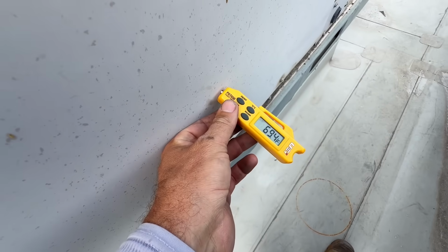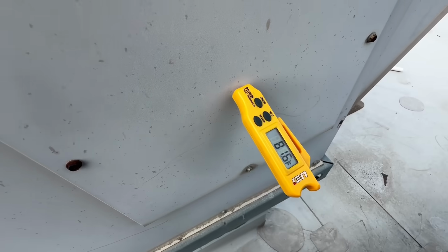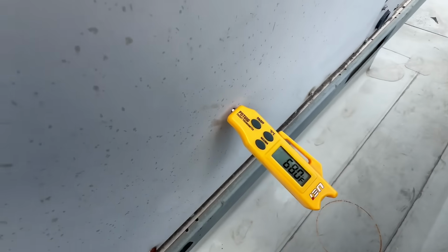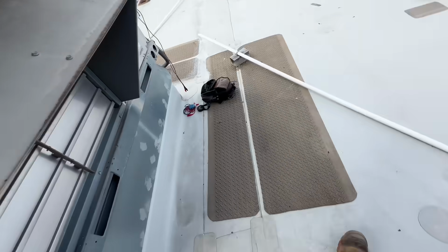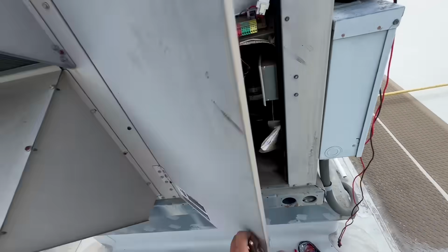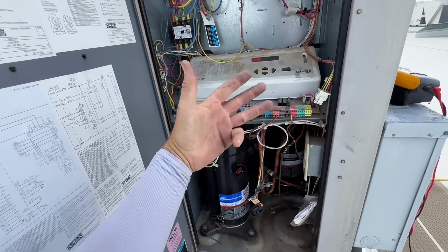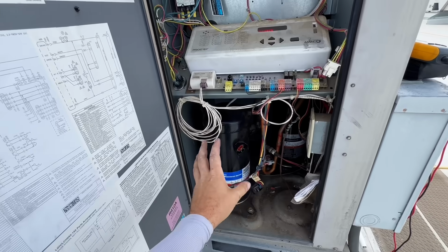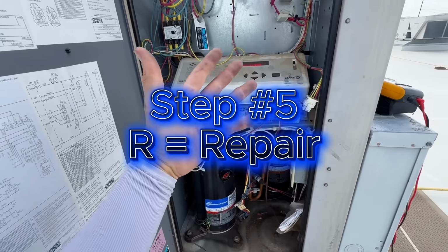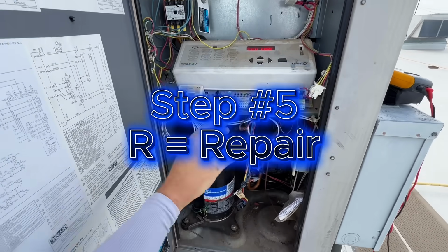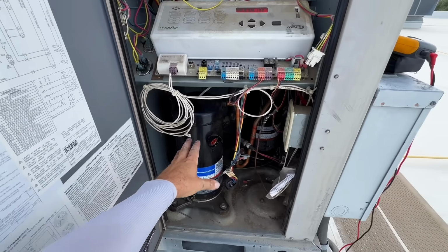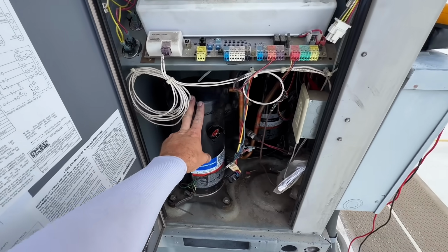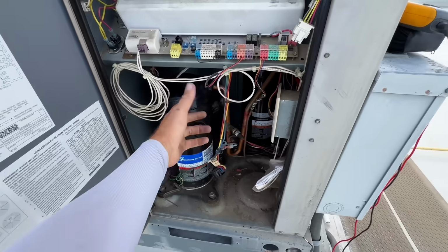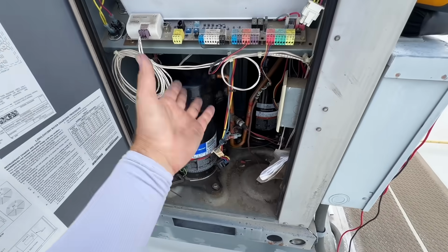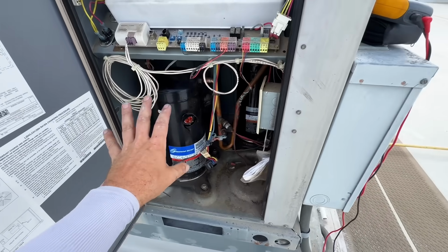Okay, this is still adjusting. So 69. Interesting. We are getting a high split for one compressor. It's pretty good. So this is really how you complete the step number 4. You ensure that what you found is actually what is going on. And now you're going to repair or recommend the repair. Obviously, if you have the approval from the customer to go ahead and replace it, simply go ahead and pull the charge, do your whole replacement, and then get them up and running 100%.